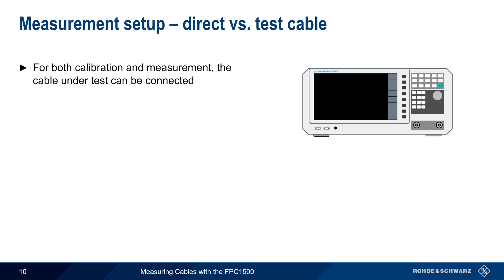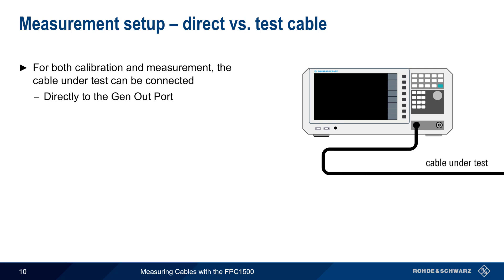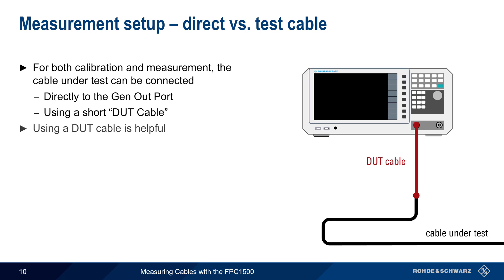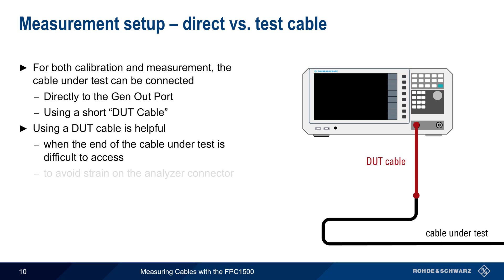Next, we'll discuss how to connect the cable under test. For both calibration and for measurement, the cable under test can be connected to the FPC in two different ways. It can either be directly connected to the Gen Output port on the front of the FPC, or it can be connected to this port using a short DUT cable. There are several reasons why using a DUT cable is helpful. The first is for cases when the cable under test's connector is difficult to access, such as when it terminates in an enclosure, or is attached to a tower or mast. Another reason is that using a DUT cable can reduce wear and tear and/or mechanical stress on the analyzer port.